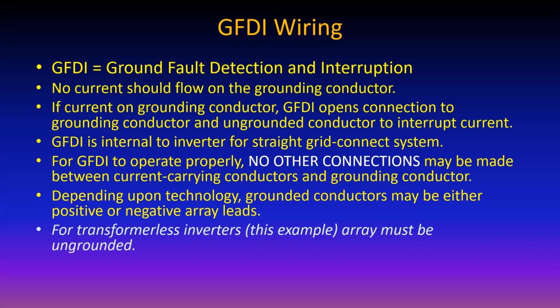And also, if you ground a conductor, in some cases, like with a 1,000-volt system, you might have some of them that have negative grounds and some that have positive grounds. With transformerless inverters, which most of them are now, and particularly this example, the array itself has to be ungrounded, but that's still covered in the inverter as far as the GFDI protection is concerned.